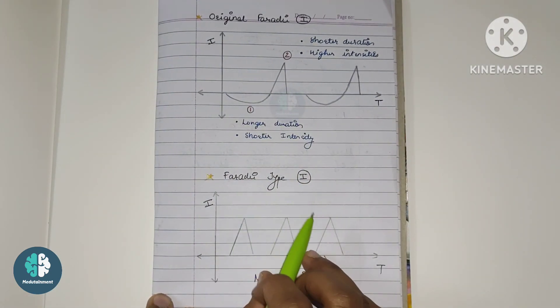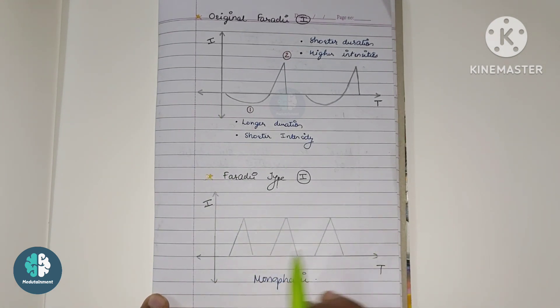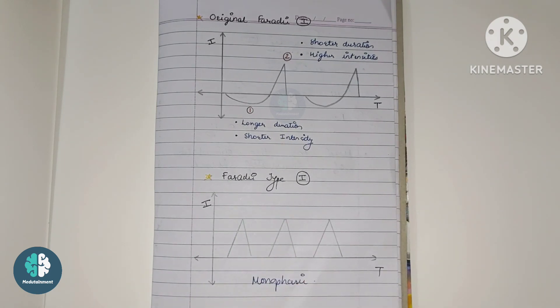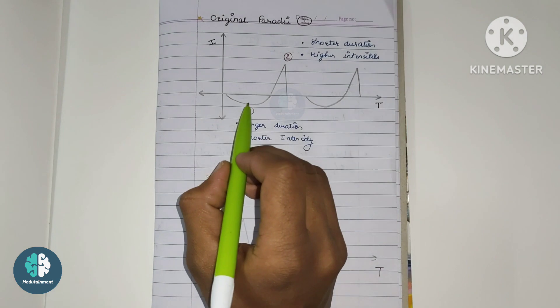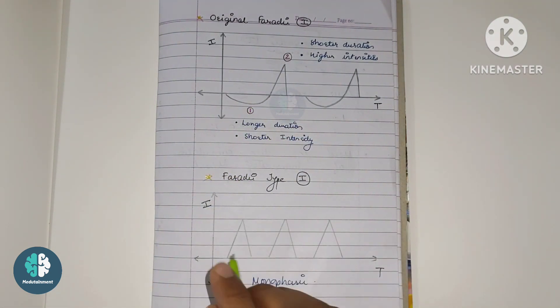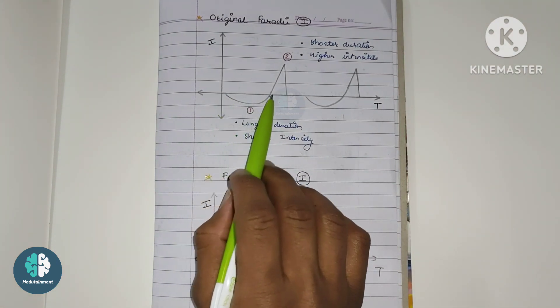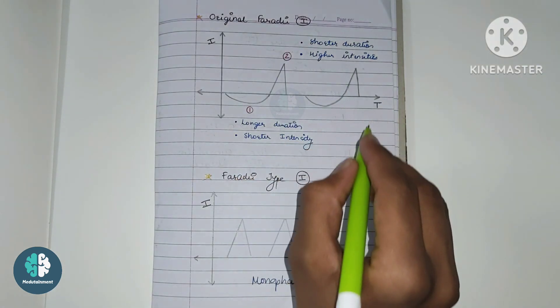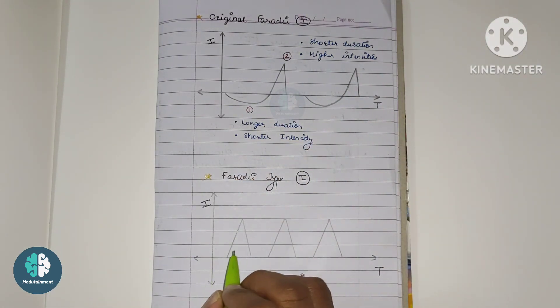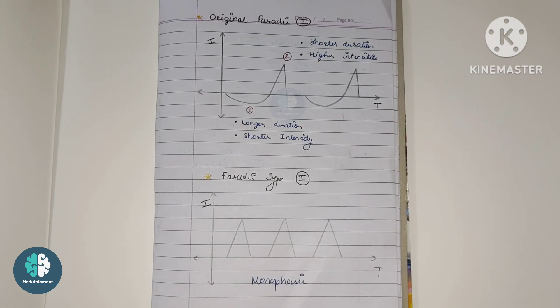For the faradaic type current, it uses a monophasic waveform with intensity and time duration plotted. In modern electronic circuits, the monophasic waveform is used because the first phase of the original biphasic waveform is not required for stimulation, since faradaic type current is interrupted DC. So the first phase is removed and only the second phase remains, giving us the monophasic faradaic type current.